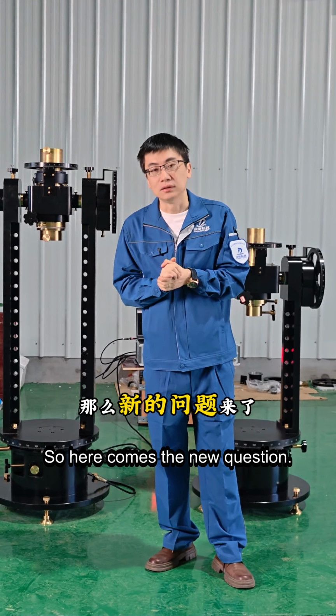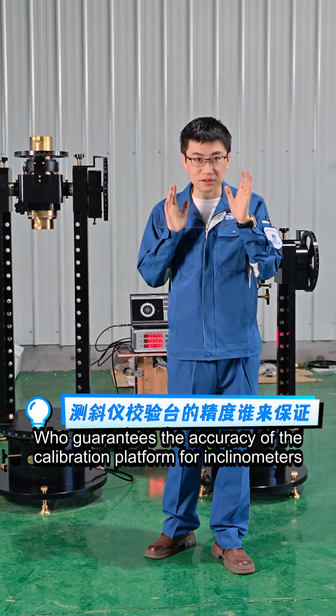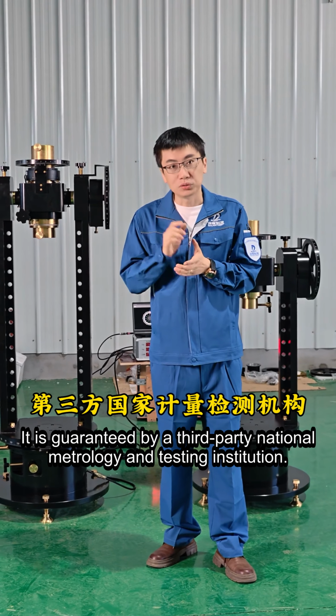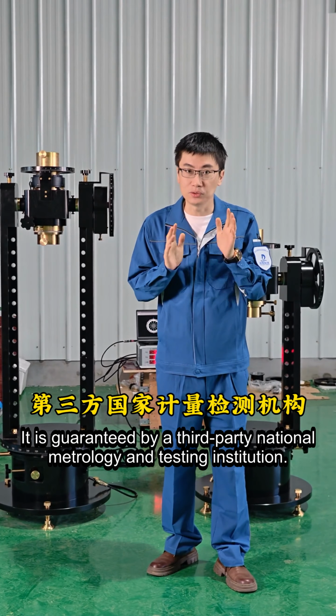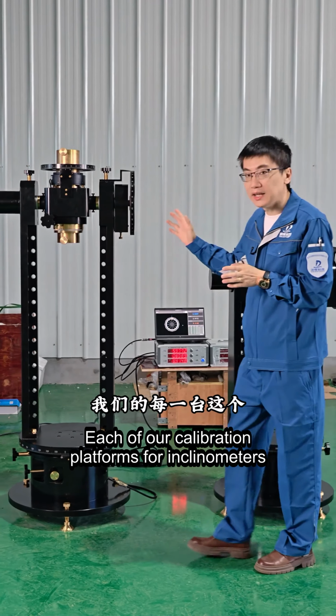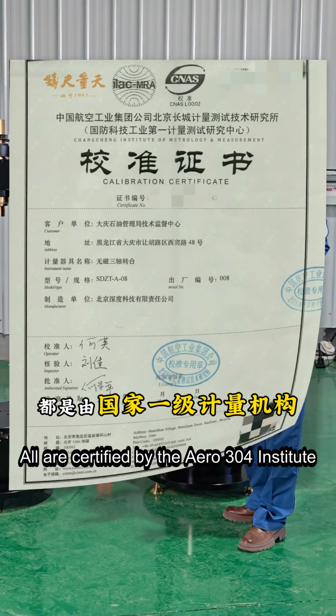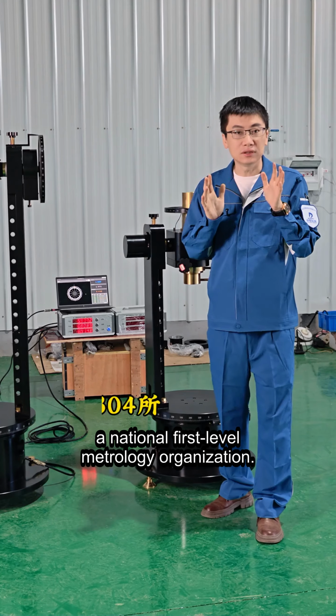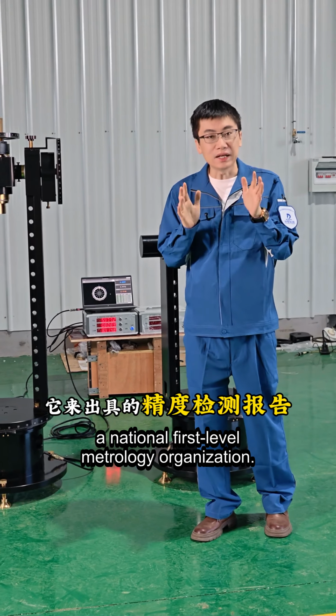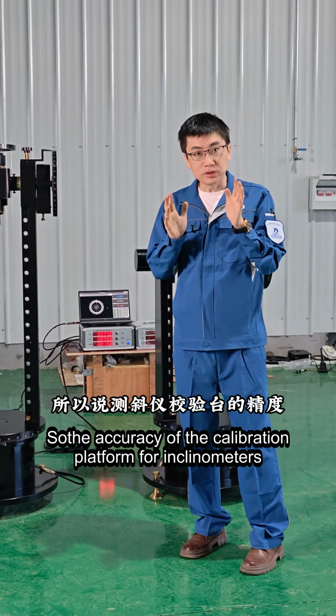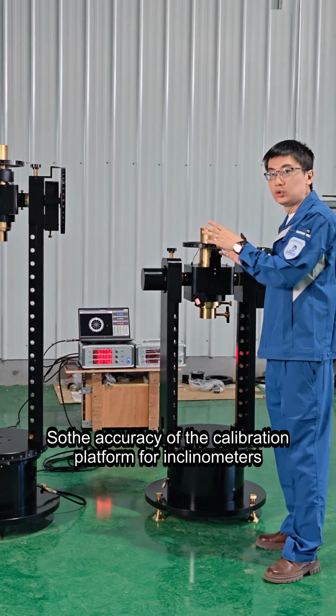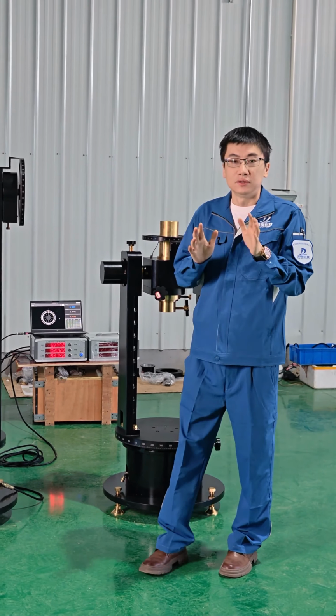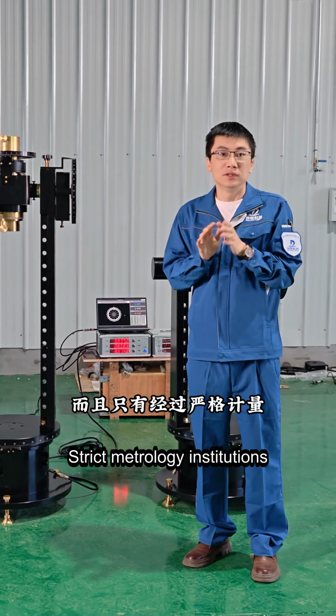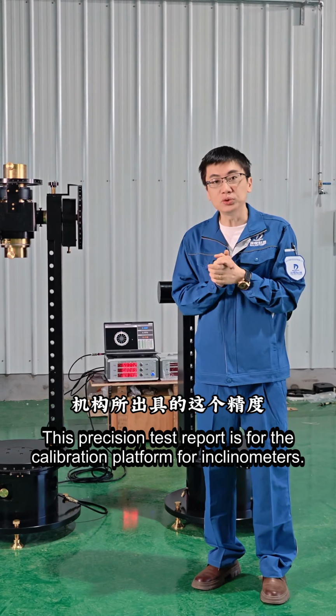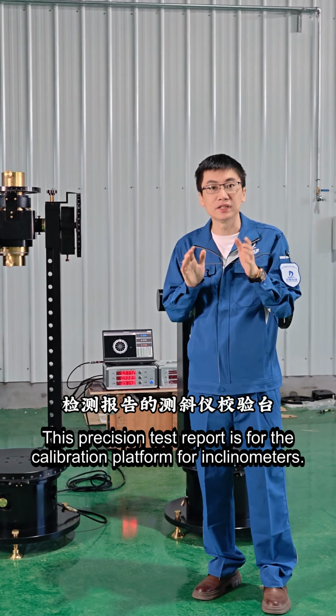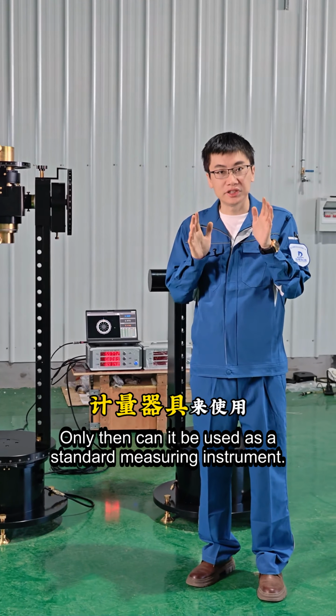So here comes the new question. Who guarantees the accuracy of the calibration platform for inclinometers? It is guaranteed by a third-party national metrology and testing institution. Each of our calibration platforms for inclinometers is certified by the Aero 304 Institute, a national first-level metrology organization. The precision inspection report it issues means the accuracy of the calibration platform for inclinometers is traceable. And only after passing strict metrology institutions, with this precision test report, can the calibration platform for inclinometers be used as a standard measuring instrument.